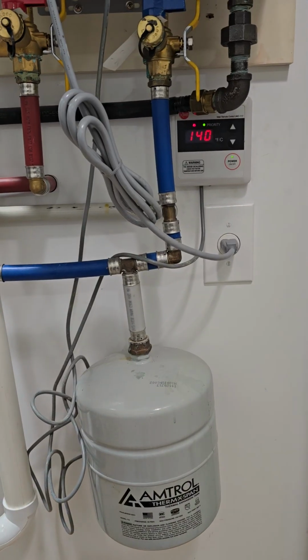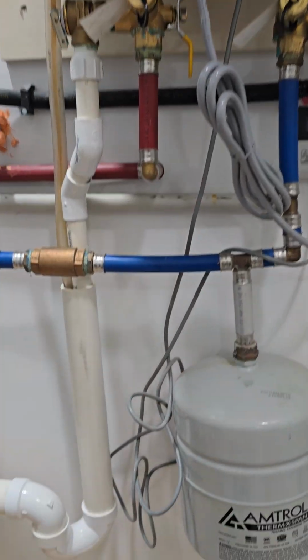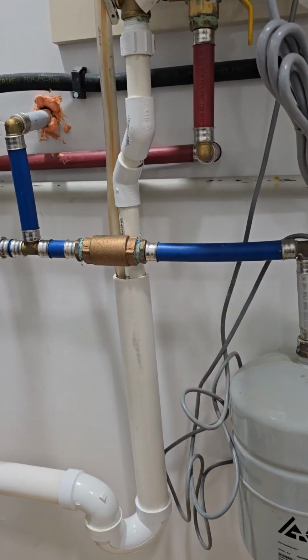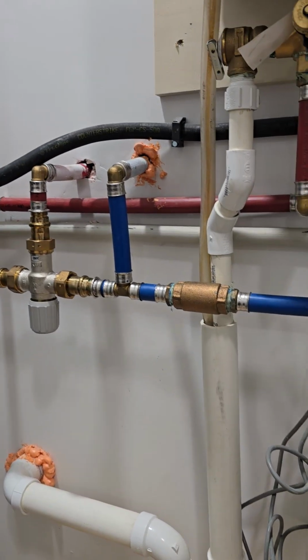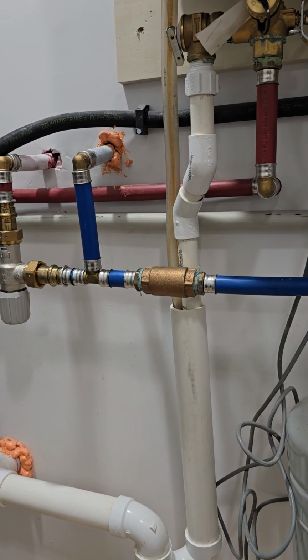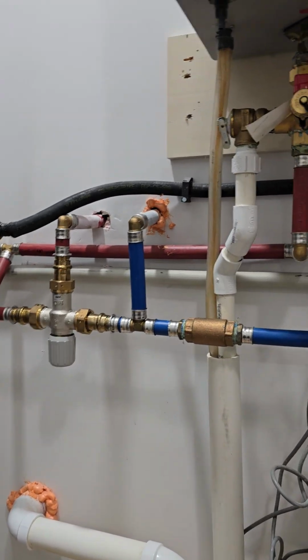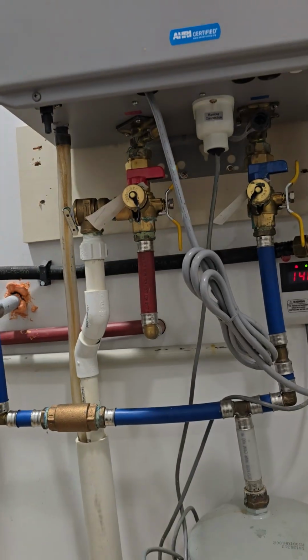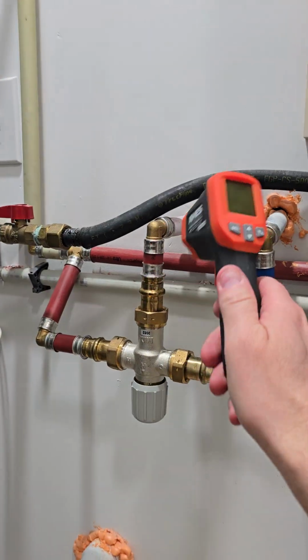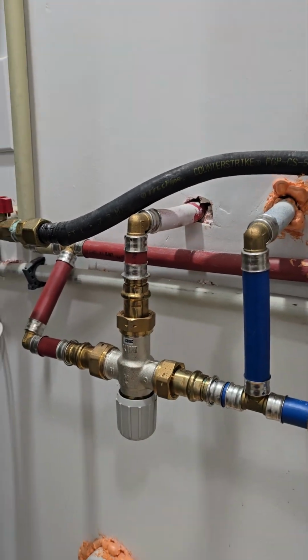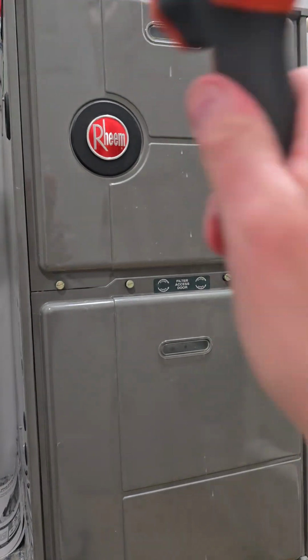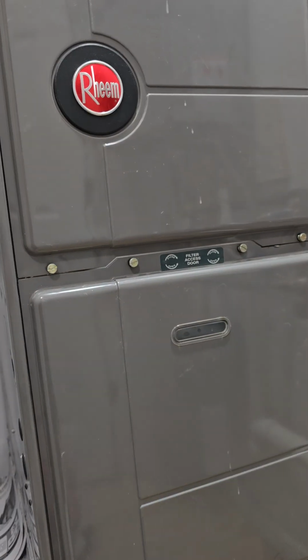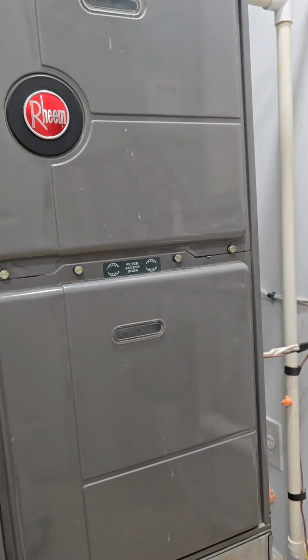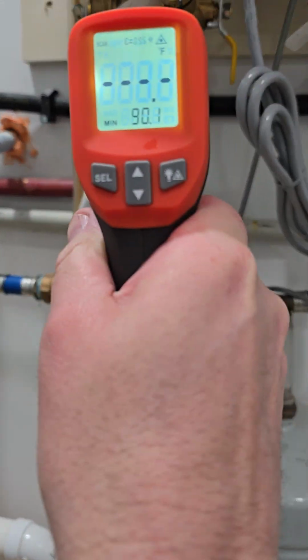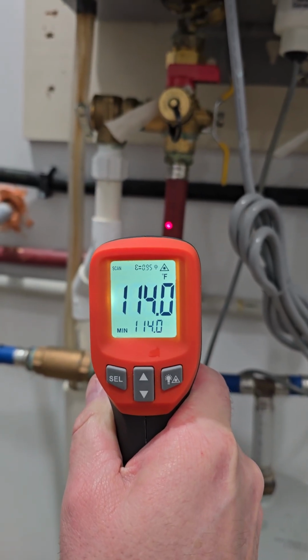The reason is this heater is effectively taking care of two zones: the zone for the water for the house, and the zone for the water that goes through a heat exchanger where air blows across it to heat the house. So we're clearly at a point where this water should be maxing out at 140 degrees.